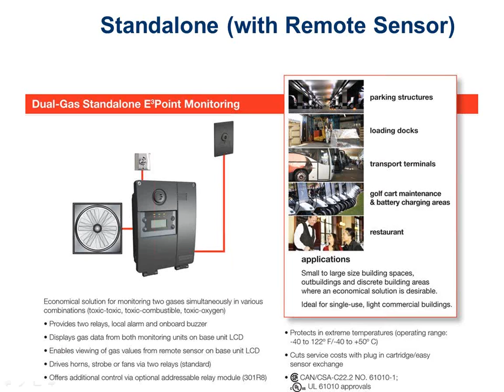Typically, these are self-healing mesh networks, so if somebody gets knocked off the wall by a car, the sensors will find a new pathway to talk to themselves. If one of them goes into alarm, it'll report back to the main panel, and they'll use that mesh network, if you will, to report it to the alarm relay panel that will start turning on exhaust fans or strobe lights or whatever I've got going on. And hopefully your exhaust fan does not look like that.